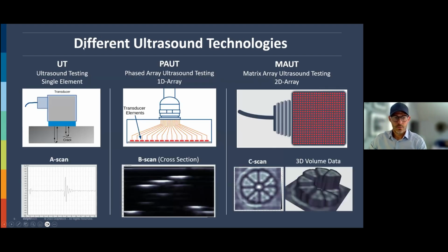So to take you through to our technology, which is on the right here, I have to take you through the journey that we've seen the last century. In the beginning of the century, the 1900s, they were still using this one element transducer, which is what I showed you in the previous slide. You put this transducer on a material that you're inspecting, and you send the sound into the material and get a reflection. Either you get a reflection from the back wall, as you see on the left side here, or you get a reflection, for example, from a crack or another void or damage.